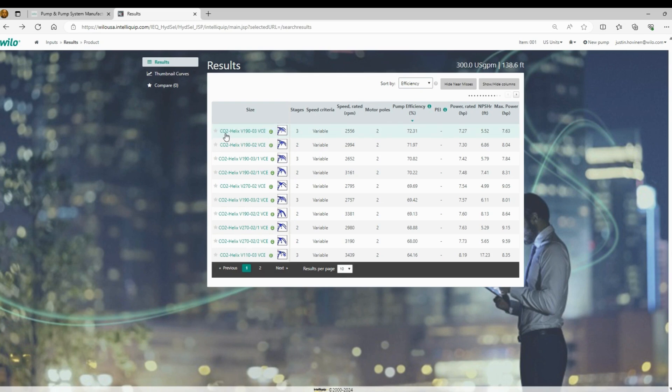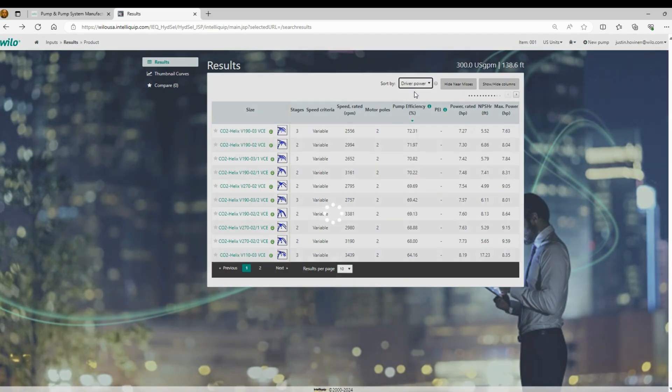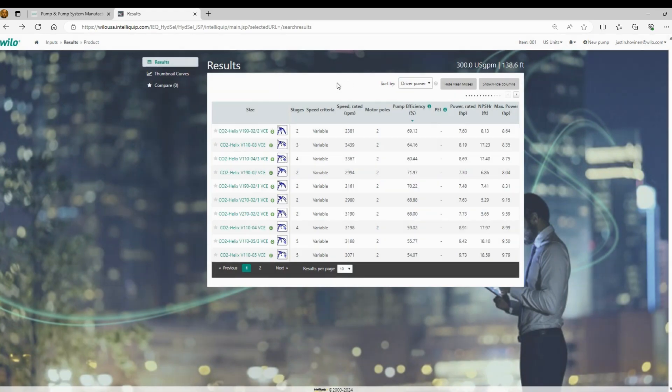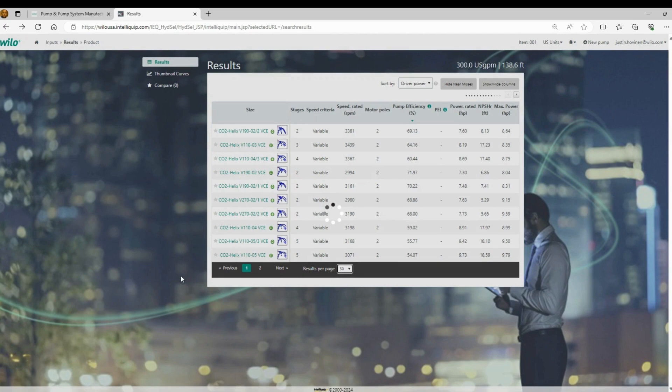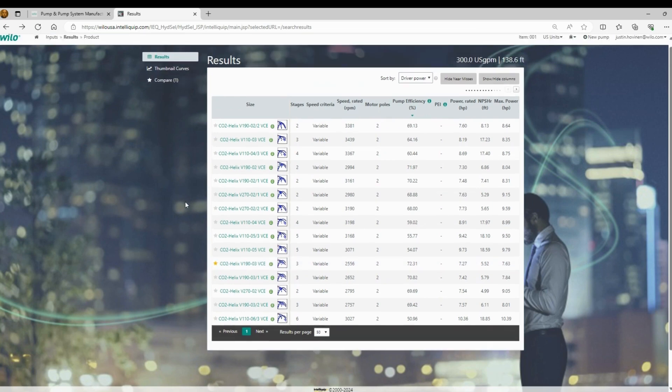So we have at the top our CO2 Helix V190-3. It has the best rated horsepower, the best efficiency, but it is hitting the primary duty condition at 2500 RPM, roughly. So if we change this to sorting by driver horsepower up at the top, we'll notice that V190-3 is no longer even on this list. So we'll actually expand the results. And we have it down here. It was actually on the second page.